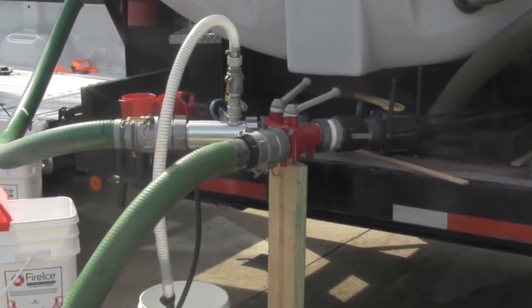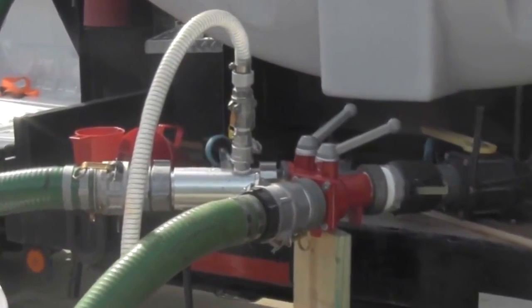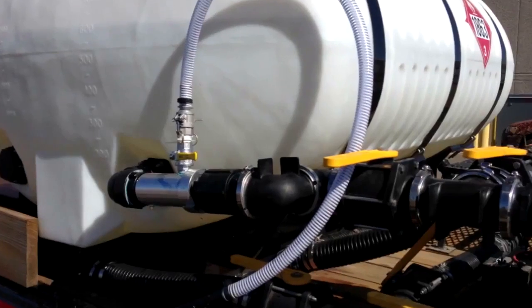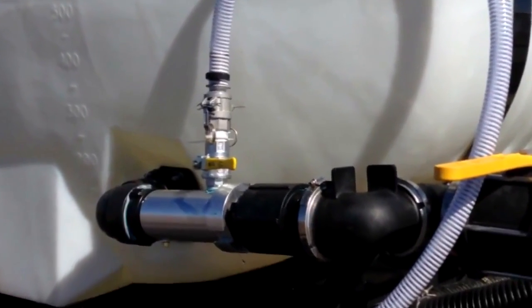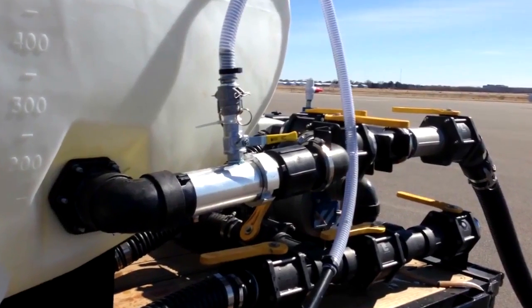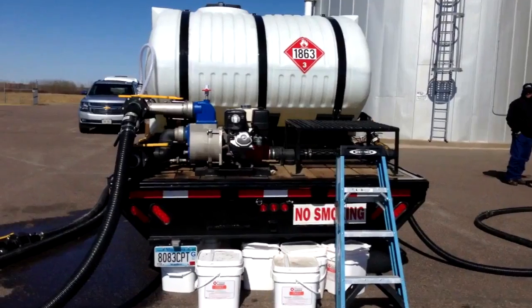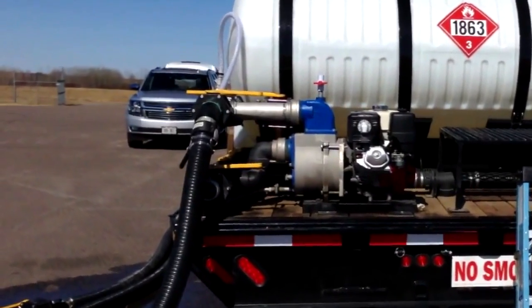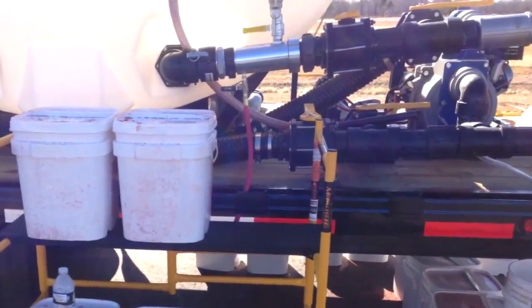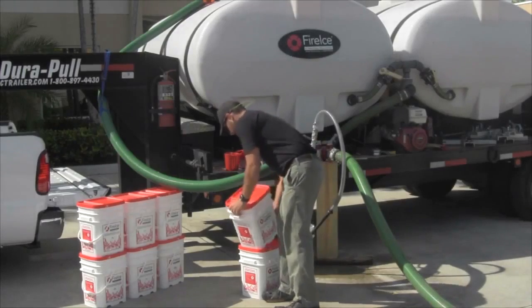The eductor must be mounted on the discharge side of the pump. This demonstration shows how the eductor can be temporarily plumbed using a 3-inch gated Y. It is recommended that whenever possible the eductor is hard plumbed, as shown in these examples. The eductor should always be mounted to recirculate into the tank — never on the load hose for direct filling. Direct filling is not recommended without consultation with a Fire Ice representative.